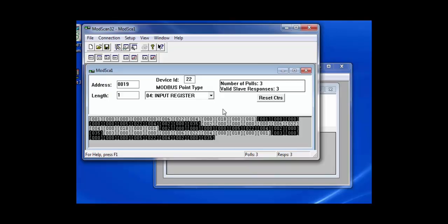Okay, so this is what I spoke about earlier, and the protocol needs this transaction identifier because of the asynchronous nature of Ethernet networks. Queries can go out without waiting on responses, and that is why we need it. So it's very, very important to recognize the transaction identifier and the fact that it increments. Okay.